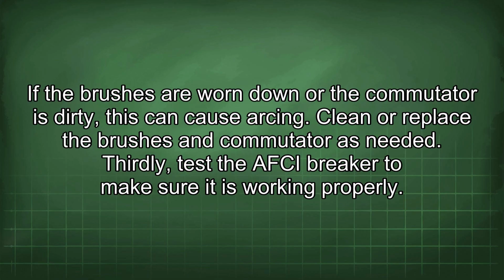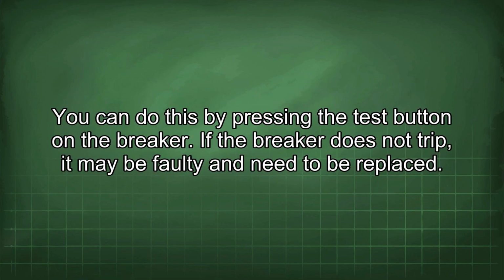Thirdly, test the AFCI breaker to make sure it is working properly. You can do this by pressing the test button on the breaker. If the breaker does not trip, it may be faulty and need to be replaced.